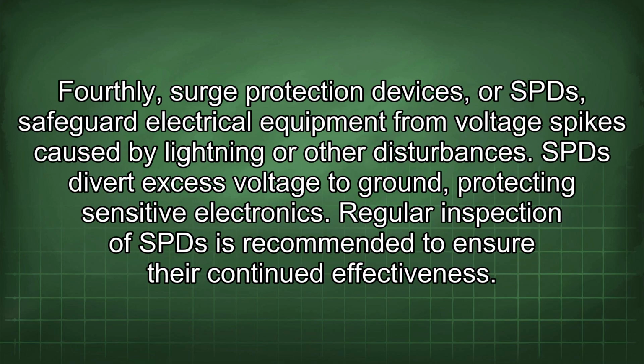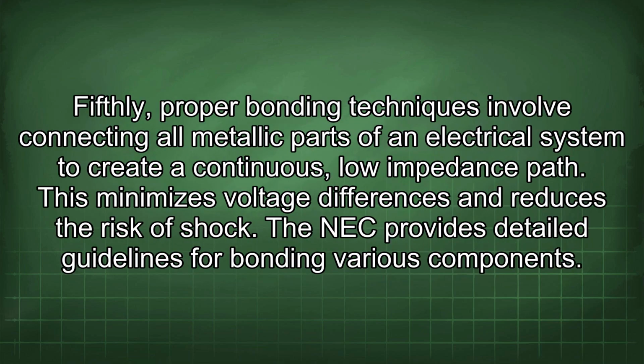Fourthly, surge protection devices, or SPDs, safeguard electrical equipment from voltage spikes caused by lightning or other disturbances. SPD divert excess voltage to ground, protecting sensitive electronics. Regular inspection of SPD is recommended to ensure their continued effectiveness. Fifthly, proper bonding techniques involve connecting all metallic parts of an electrical system to create a continuous, low-impedance path. This minimizes voltage differences and reduces the risk of shock. The NEC provides detailed guidelines for bonding various components.